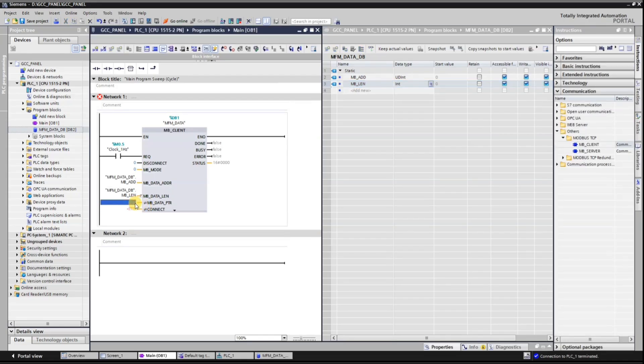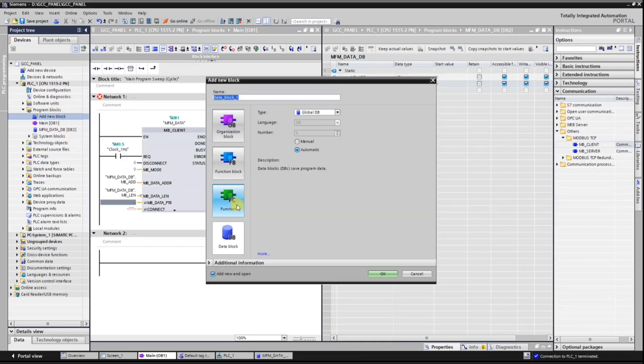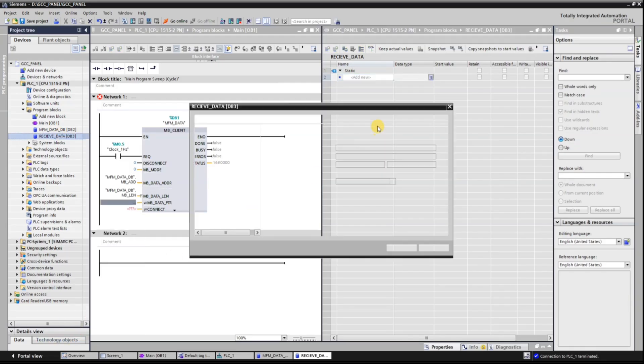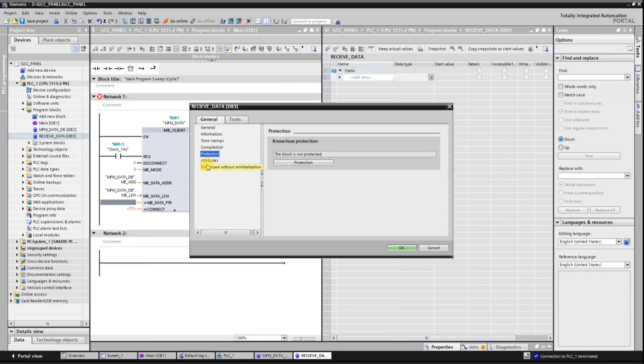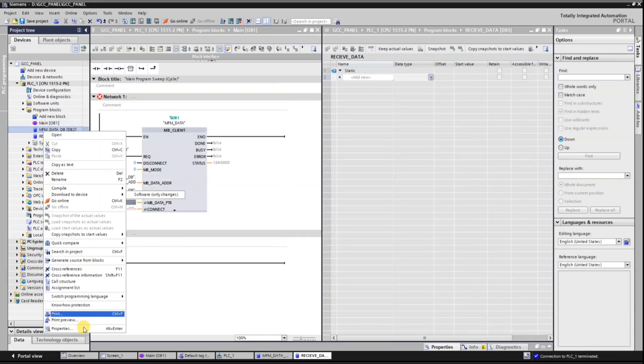Now we drag and drop our DB address into MB client. There are two other options: MB data PTR and connect PTR. MB data PTR means where you want to receive data in your PLC DB or address. Connect PTR is where we need to write our server properties. Here we need to disable optimized block access in our DB.